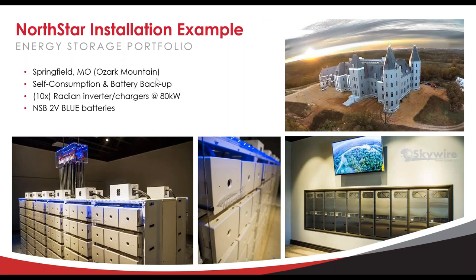Here's another example. This is based in the Ozark Mountains in Missouri. This time they're using 10 stacked inverters that is up to 80 kilowatts with 6 48-volt strings of the NSB Blue 2-volt batteries. And it's really designed to be self-consumption with battery backup, with all this equipment.